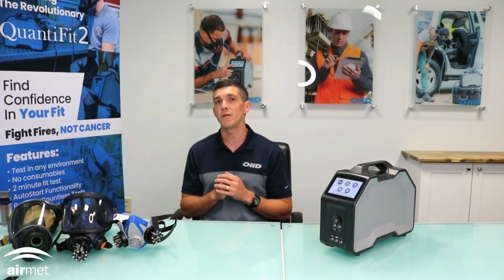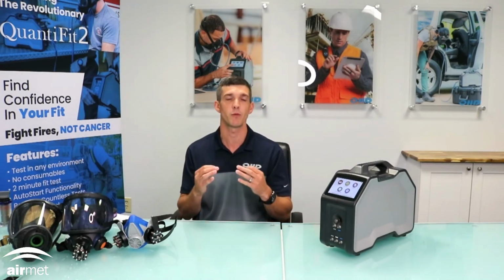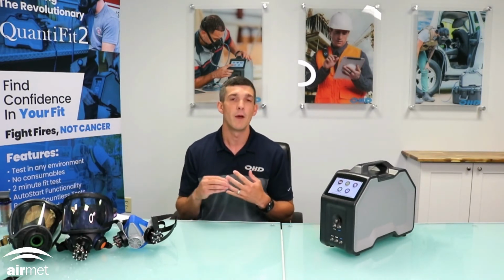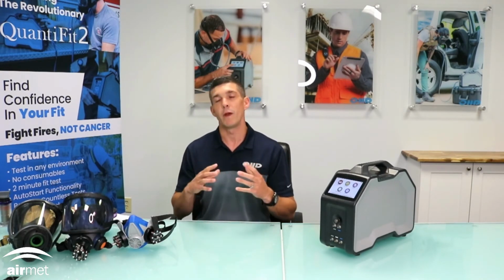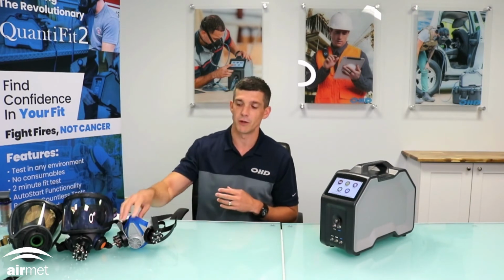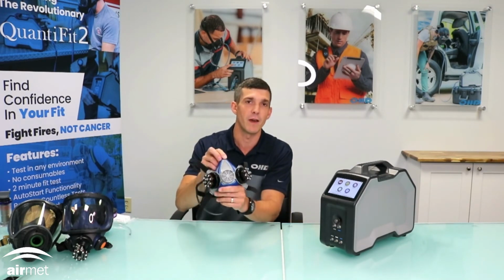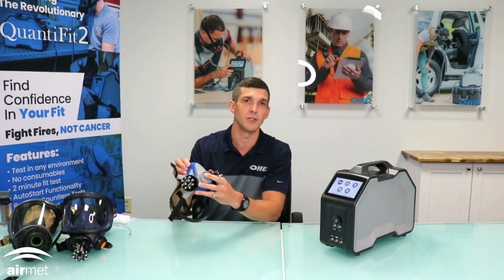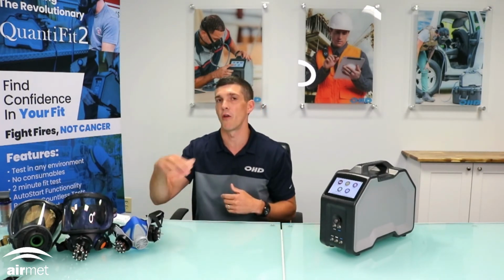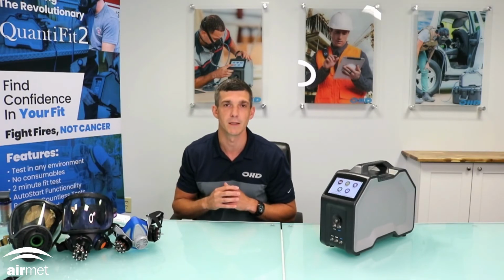The only limitation with our technology would be the testing of disposable respirators. So if your respirator is an N95 or a respirator at that level of a disposable nature of protection, we cannot fit test those with controlled negative pressure. So really any elastomeric half-face respirator and up, controlled negative pressure is the optimal technology to fit test those respirators, all the way up to your CBRNE level test. So now let's take a closer look at the QuantiFit2 and its new features and benefits.